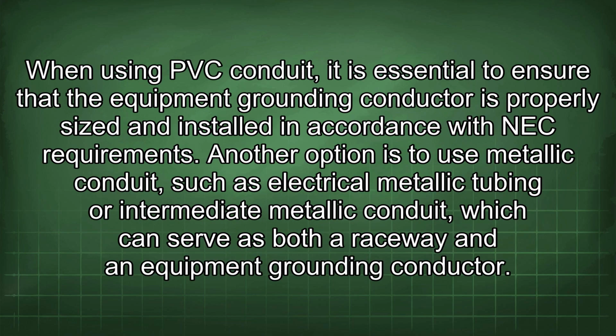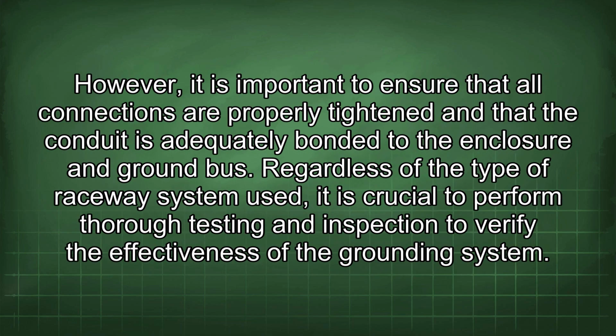However, PVC conduit is non-conductive and therefore requires a separate equipment grounding conductor to be installed within the conduit. When using PVC conduit, it is essential to ensure that the equipment grounding conductor is properly sized and installed in accordance with NEC requirements. Another option is to use metallic conduit, such as electrical metallic tubing or intermediate metallic conduit, which can serve as both a raceway and an equipment grounding conductor. However, it is important to ensure that all connections are properly tightened and that the conduit is adequately bonded to the enclosure and ground bus.